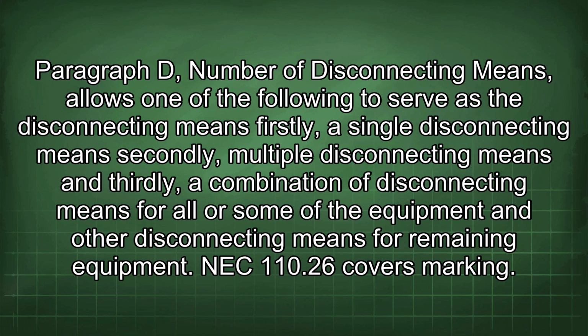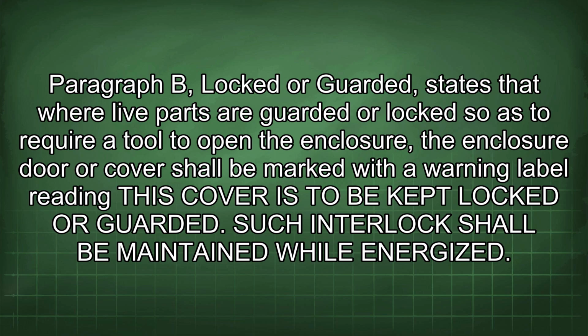NEC 110.26 covers marking. Paragraph B, Locked or guarded, states that where live parts are guarded or locked so as to require a tool to open, the enclosure door or cover shall be marked with a warning label reading "This cover is to be kept locked or guarded." Such interlock shall be maintained while energized.